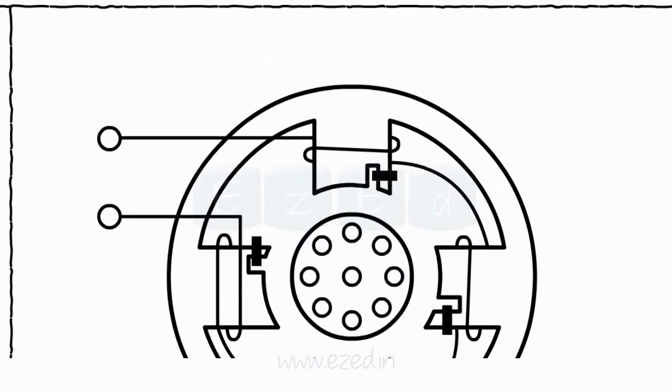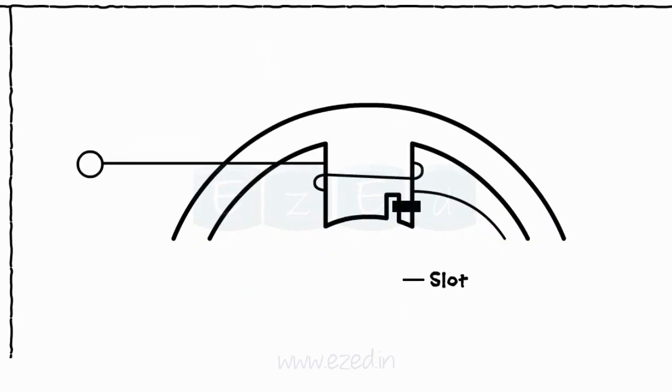The third type is shaded pole induction motor. In this motor, every laminated pole has a slot cut across the laminations approximately one-third distance from the edge. A short-circuited copper coil known as a shading coil is placed around the small part of the pole. This part of the pole is known as a shaded part and the other as a non-shaded part.